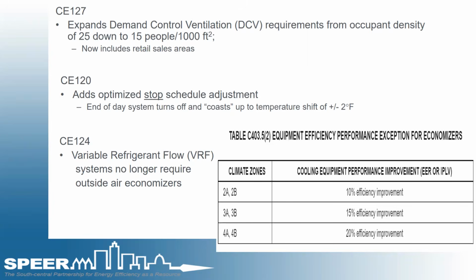So that was broken in the 2015 code. If any of you are designing mechanical systems in climate zone 2 or 3A, in Dallas, Houston, Corpus, wherever, and you don't want to put an economizer on there and you've always been made to - I know me as a code official, and most code officials who use common sense and can apply it to the intent of the code - just let them know, hey, they fixed that.